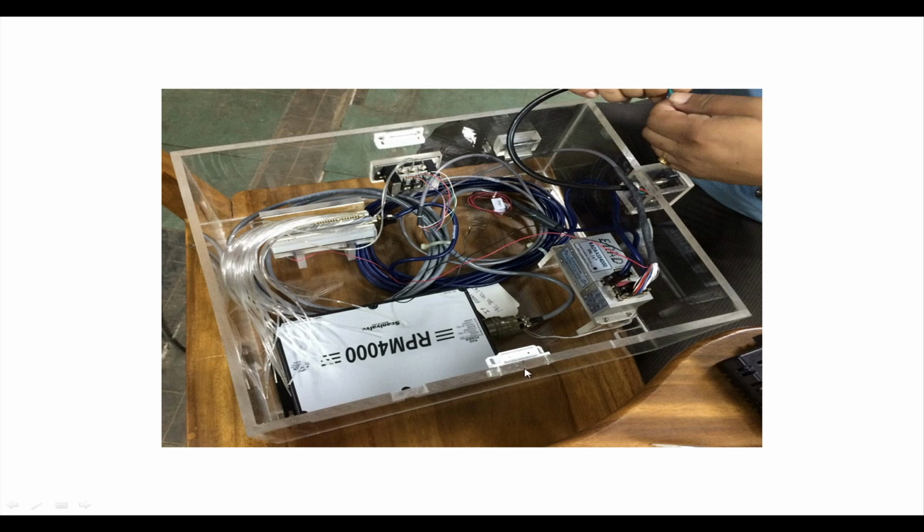Yeah, I will just try to tell you broadly. This unit is going to get the power supply from the AC line and give the DC power to several subunits here. Then this has some data cards inside, and this unit is a solenoid valve unit, which can be used to provide the control pressure to some ports here on the pressure scanner.